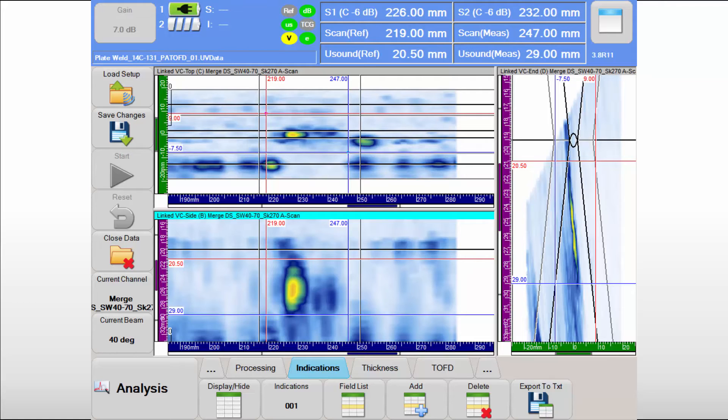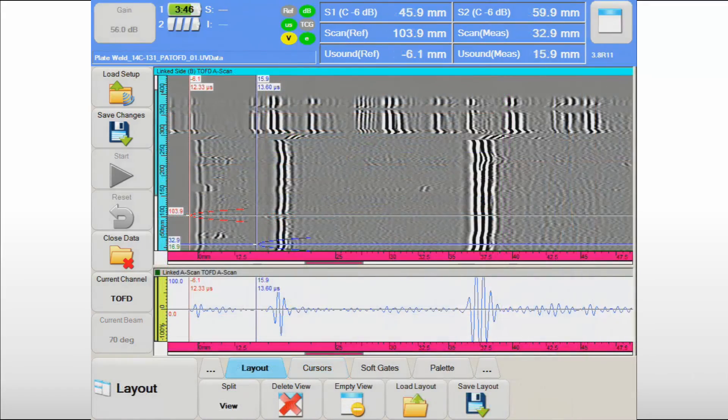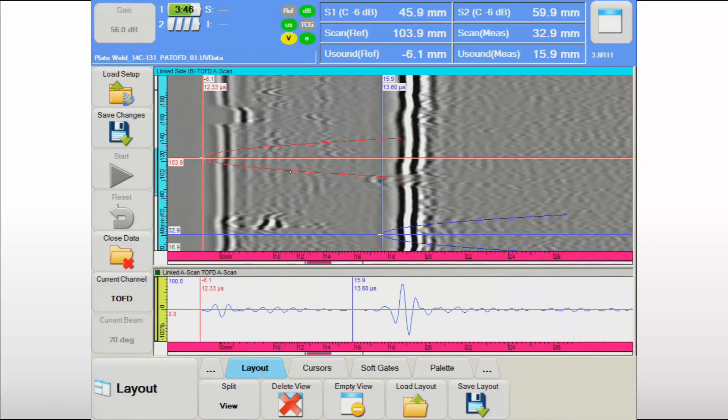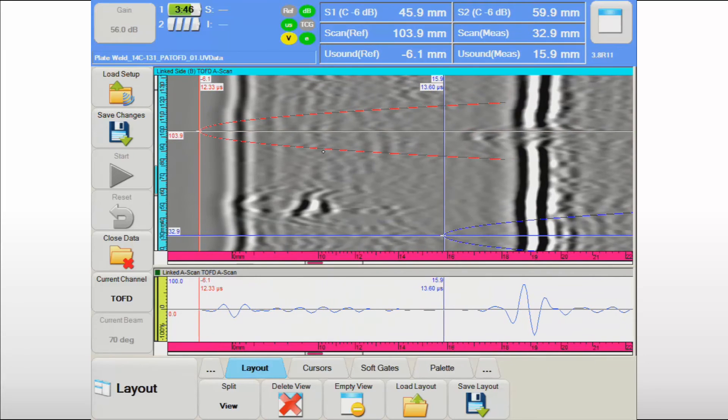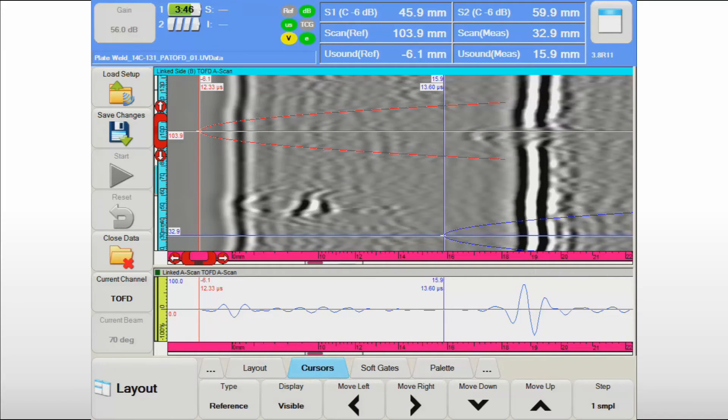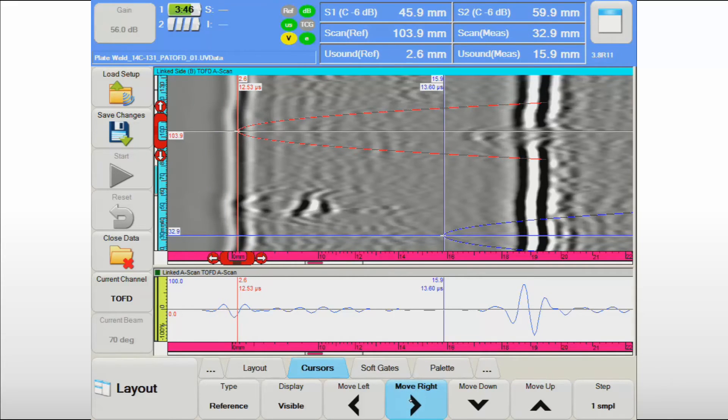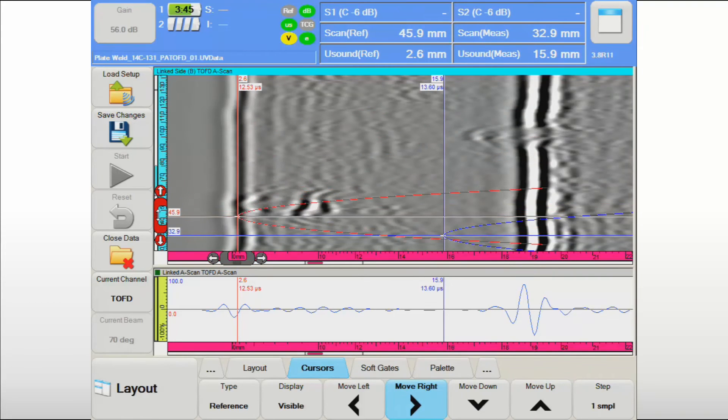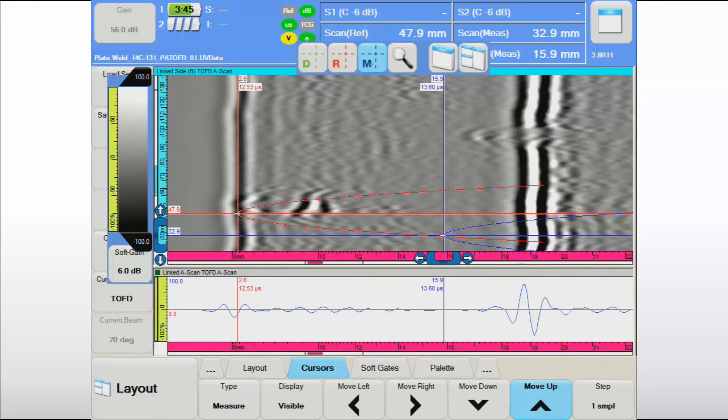The TOFD technique is very powerful for detection and sizing of embedded flaws, and for accurate height sizing of cracks. UltraVision Touch software includes all measurement tools to facilitate the analysis of TOFD data. Additionally, the software provides the typical processing tools recommended by the applicable codes, like lateral wave straightening and lateral wave removal. The lack of fusion that was clearly detected in the pulse echo phased array data is confirmed in the TOFD data.